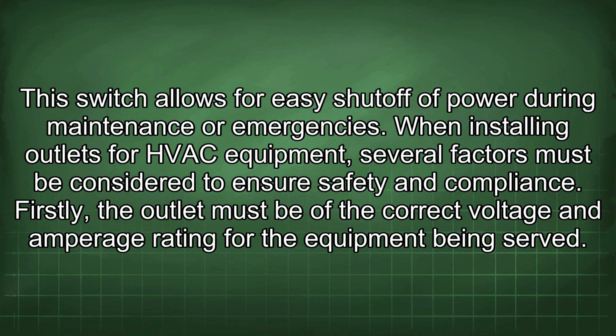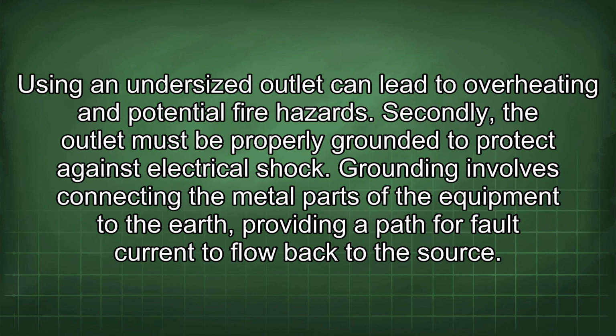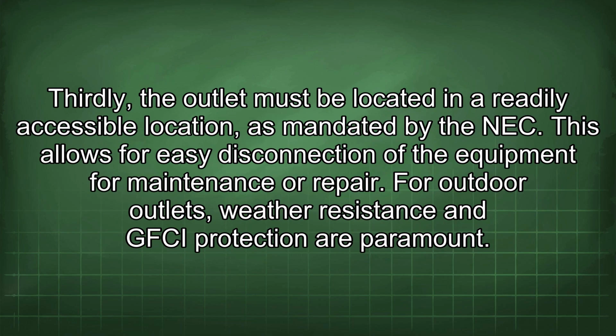When installing outlets for HVAC equipment, several factors must be considered to ensure safety and compliance. Firstly, the outlet must be of the correct voltage and amperage rating for the equipment being served. Using an undersized outlet can lead to overheating and potential fire hazards. Secondly, the outlet must be properly grounded to protect against electrical shock. Grounding involves connecting the metal parts of the equipment to the earth, providing a path for fault current to flow back to the source. Thirdly, the outlet must be located in a readily accessible location, as mandated by the NEC. This allows for easy disconnection of the equipment for maintenance or repair.